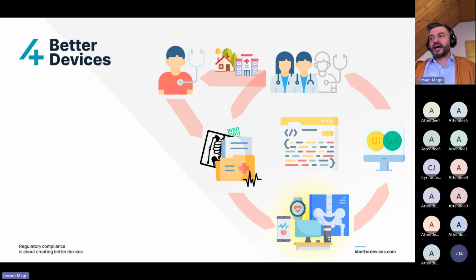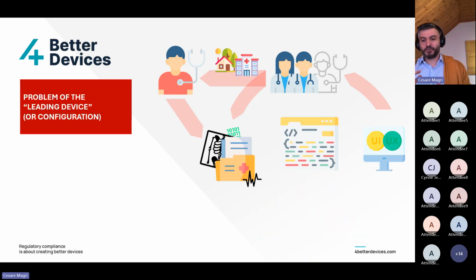Okay, but the point is the manufacturer of the software in their technical documentation will have to specify exactly what is going to be this hardware platform on which the software is going to run and is going to be able to get this input and output. So this is not something that the manufacturer provides physically, but only in terms of information. Okay, and this is a problem sometimes because there is a feeling, or sometimes it is almost forgotten. So the idea is, okay, I can provide the software without providing this specification of the hardware, and that leads to problems.